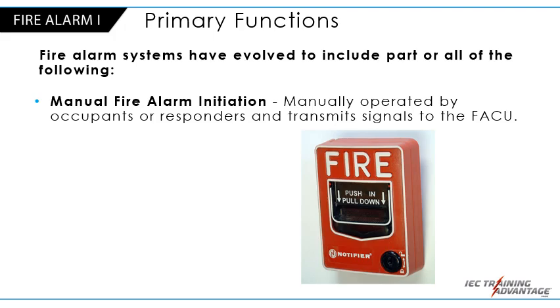Fire alarm systems have evolved to include part or all of the following: manual fire alarm initiation, manually operated by the occupants or responders and transmit signals to the FACU. These manual fire alarm boxes are typically placed at exits on each floor of the building, where required by other codes such as International Building Code. A manual fire alarm initiation device is a pull station or any other kind of switch or trigger that requires an occupant to interact with the device.